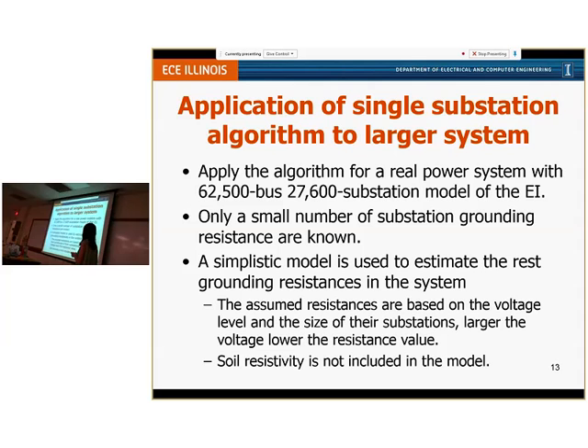Now we apply this algorithm to a real power system with 62,500 buses and 27,600 substations. It is a model of the EI, and only a small number of grounding resistance values are known in this system. So we use a simplistic model to estimate the rest of the grounding resistance. In this model, the value of grounding resistance only depends on the voltage level of the substation and the size of the substation, which means how many lines connect into it. And the soil resistivity is not included in this model, although in practice, the soil resistivity has a significant impact on the grounding resistance.